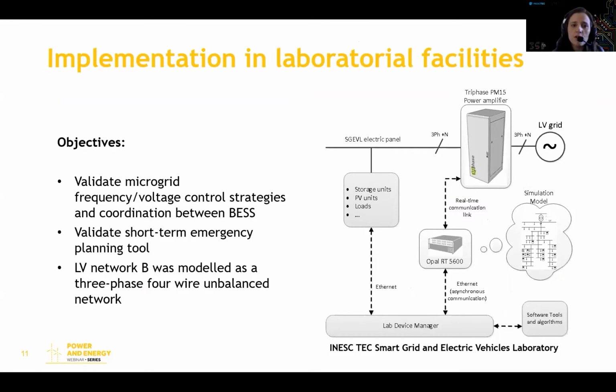But first, before going to the pilot, we wanted to validate the control strategies and the tool in the laboratory. And to do that, we used our power hardware-in-the-loop test setup, where we simulated and modeled the pilot network in the real-time digital simulator, and also some of the larger storage device units that provide the grid forming capabilities according to the manufacturer models. And we added one of the grid supporting storage devices that we dispatched and that was connected to the real infrastructure of the laboratory.